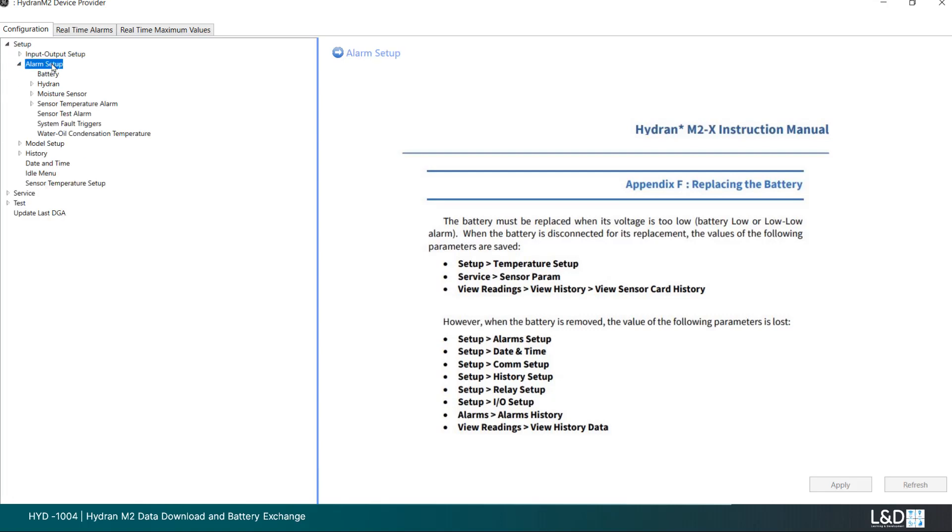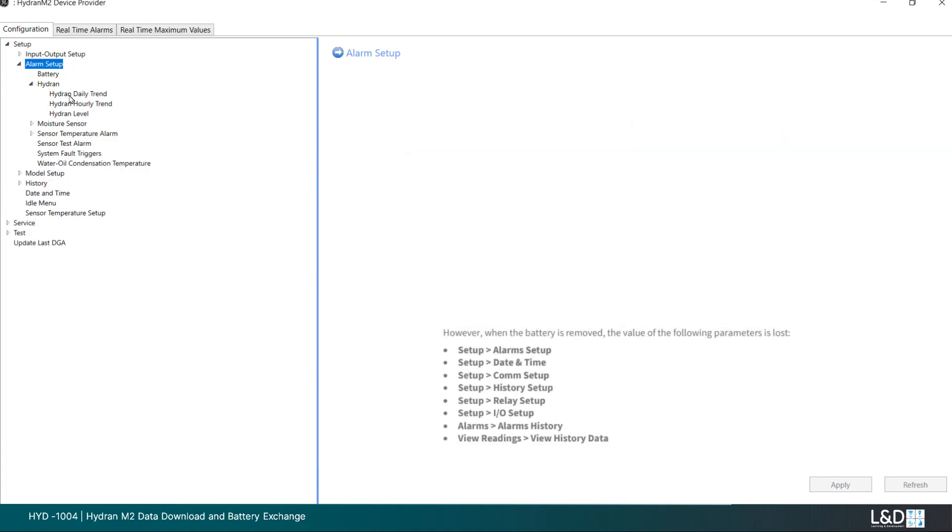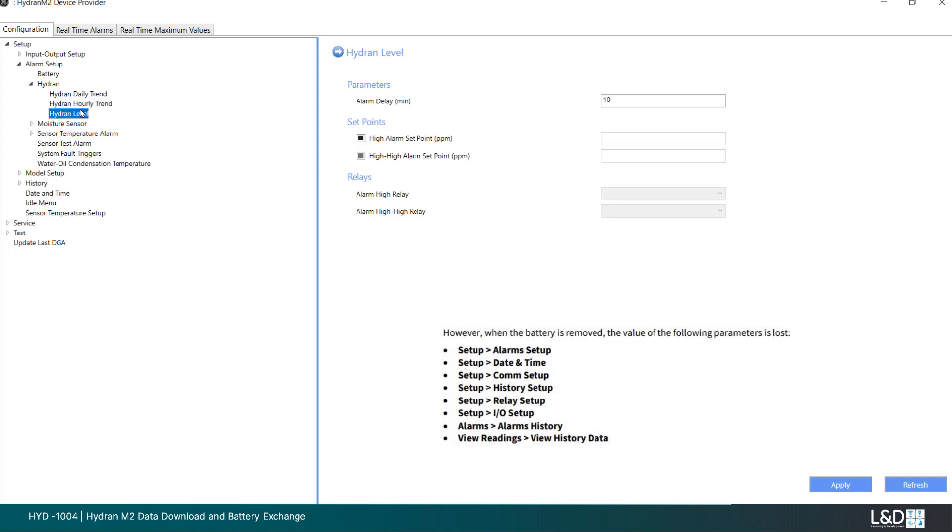Refer to the equipment support manual for Hydran removal or watch the relevant product video in this set. Replacing the battery could be for one of the following reasons: system alarm of battery depletion, recognized loss of date and time after system re-energization, or as part of a proactive equipment care program.